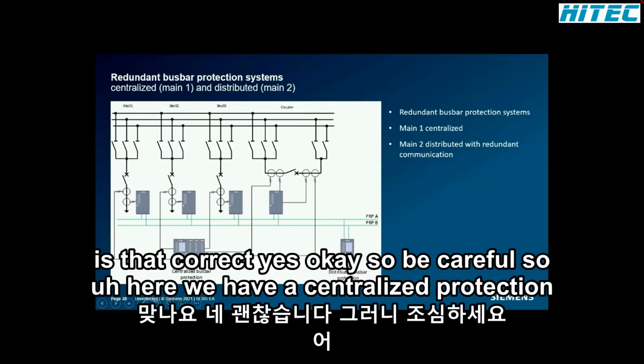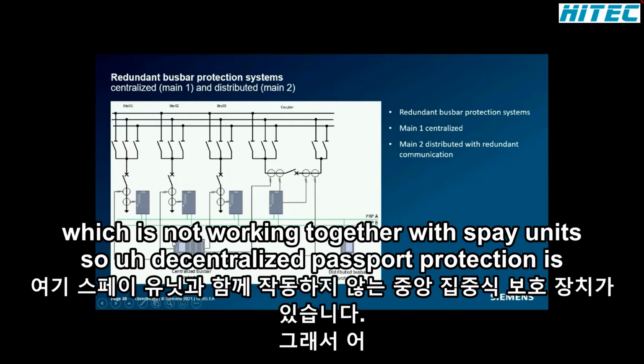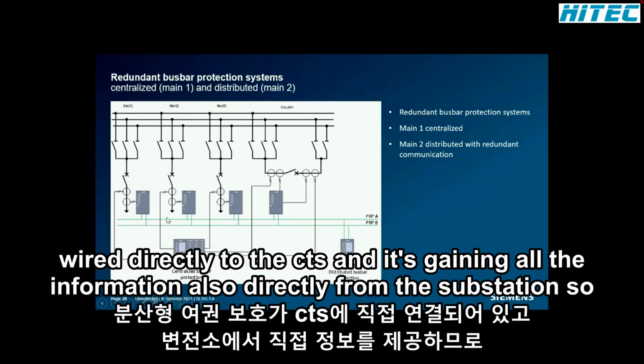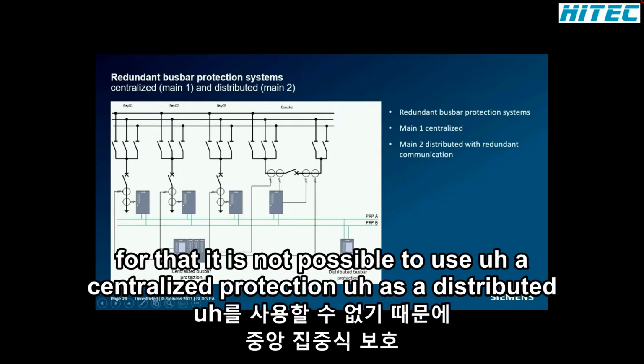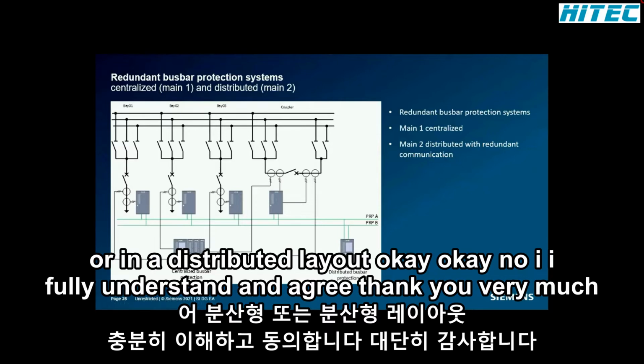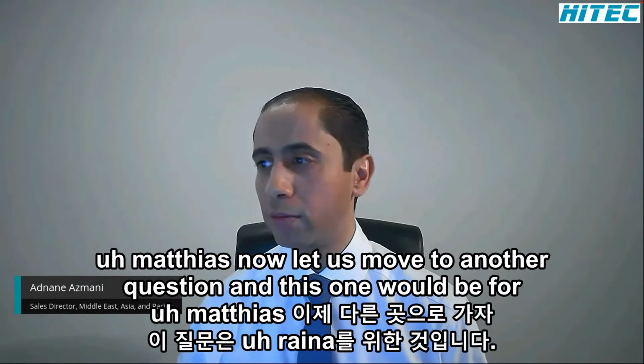So here we have a centralized protection, which is not working together with bay units. The centralized busbar protection is wired directly to the CTs, and it's gaining all the information also directly from the substation. So for that, it is not possible to use a centralized protection in a distributed layout. Okay. No, I fully understand and agree. Thank you very much, Matthias.